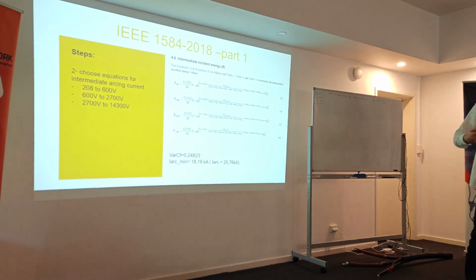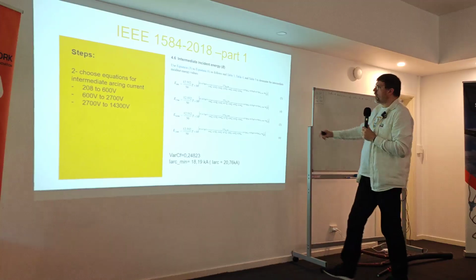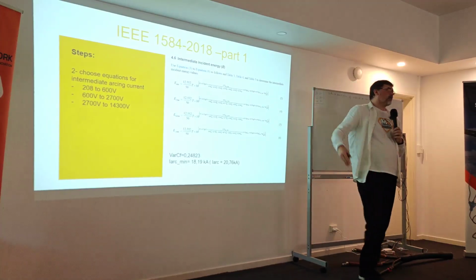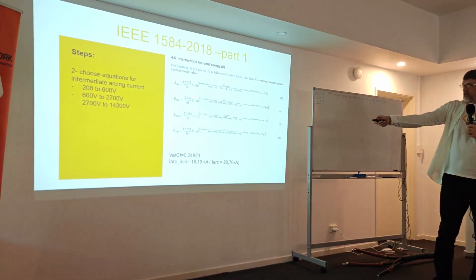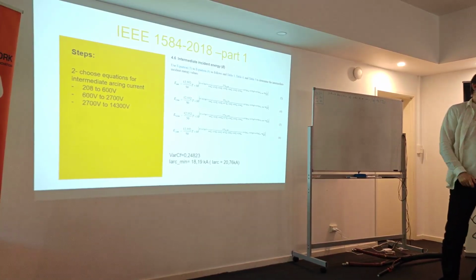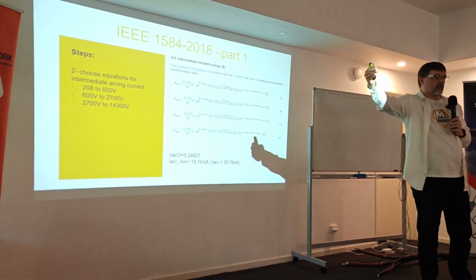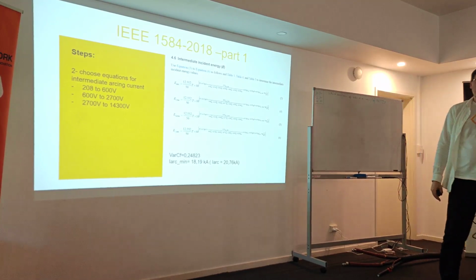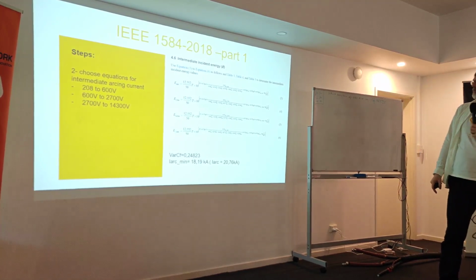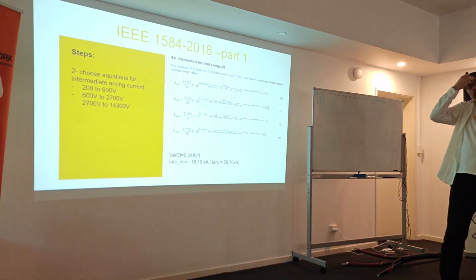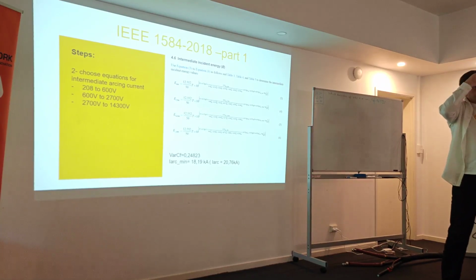And when we calculate it, you end up with something like 25 joules, which turns joules into calories, which was going like 5 calories per square centimeter, which I have to open Excel now because maybe I didn't fill it in. And this will end up your calculation on the energy. And the last thing you have to calculate is the arc flash boundary, which is also like this equation, but luckily we just use the same coefficient factors with just a different equation. So you estimate the difference, how far you have to stand to reduce the energy below 1.2. I have to open the Excel file because maybe I didn't do it in the presentation. And that's pretty much how you calculate the arc energy for one point.